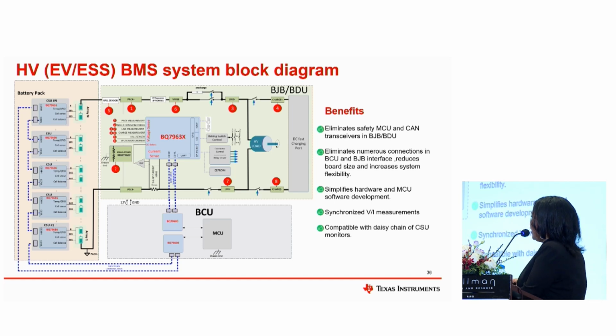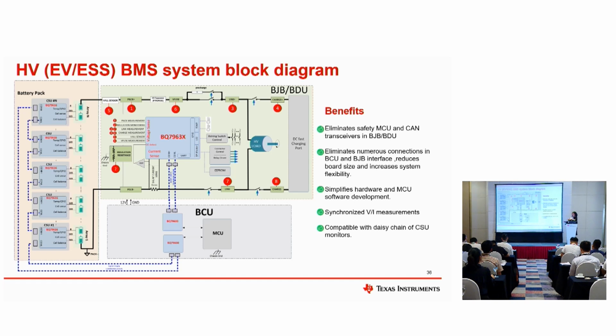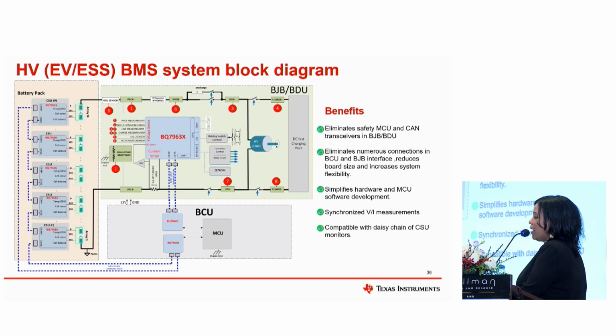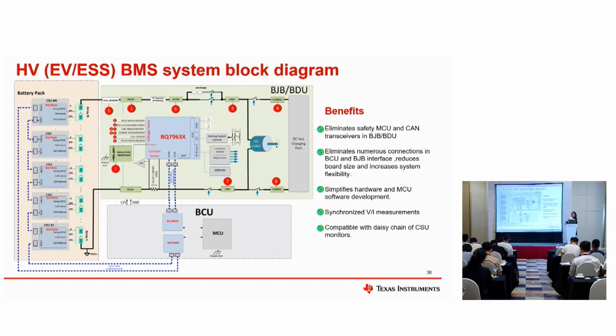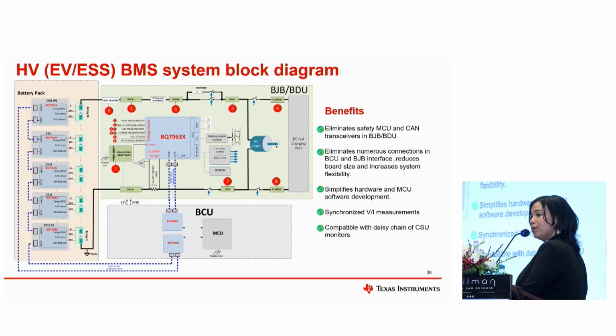Here we have what we call BCU, or battery control unit, and this is where your low voltage system lies. So you have your MCU and your isolation. You can use something like the BQ79600, which is a communication bridge to transfer from the MCU UART communication to your daisy chain, and you can add that into your system to keep it isolated in the low voltage.